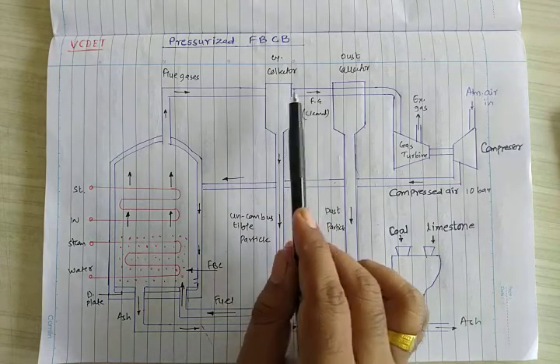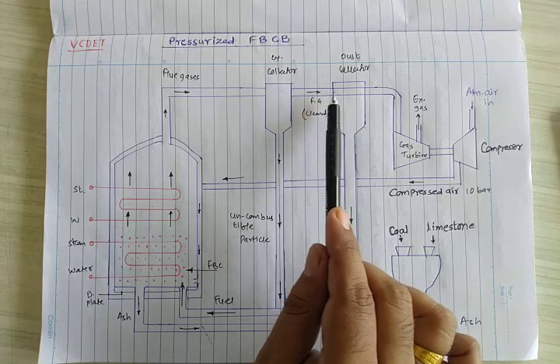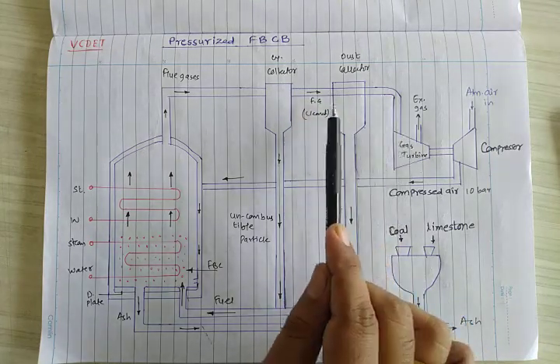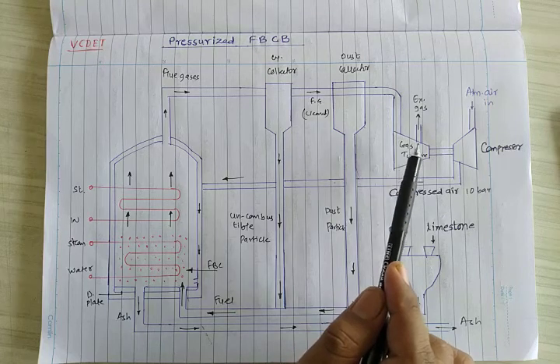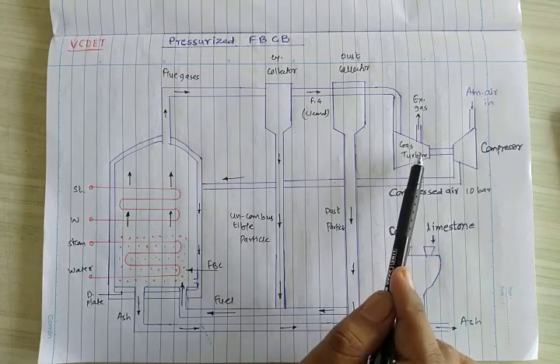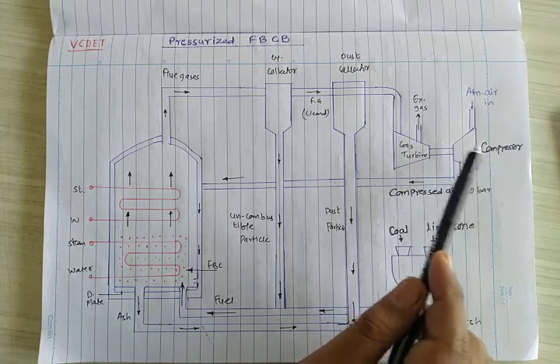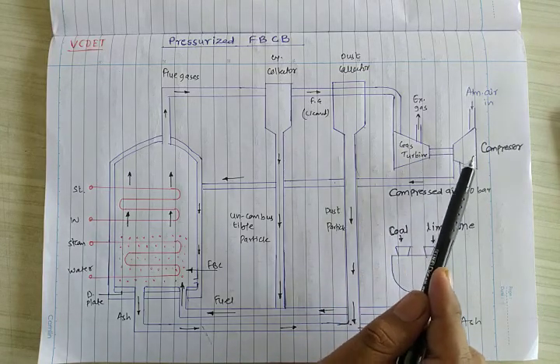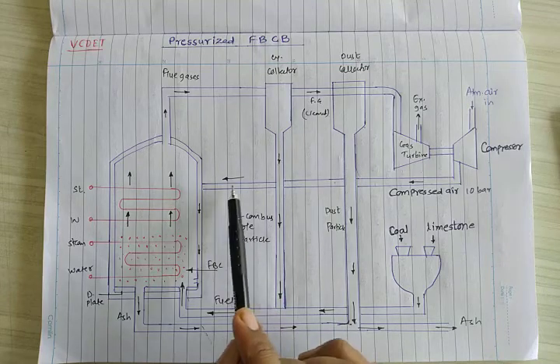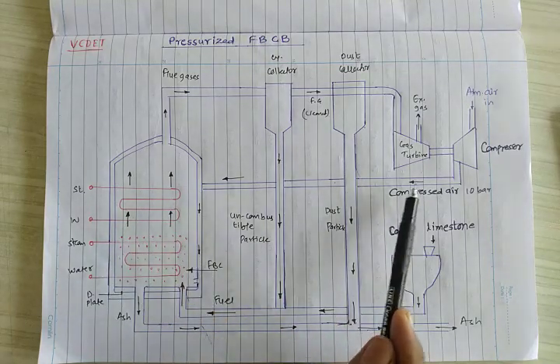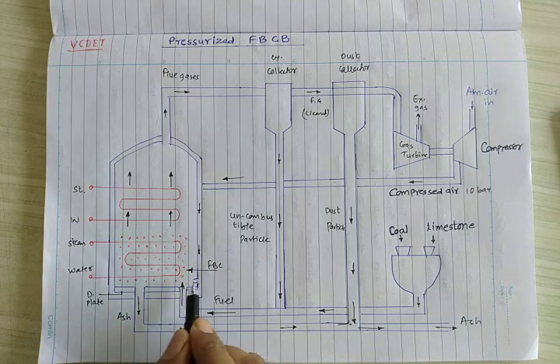The flue gases are forwarded, cleaned, and then forwarded towards the dust collector. From the dust collector they go towards the gas turbine. The clean flue gases are transported towards the gas turbine, which runs the compressor — the compressor shaft is coupled to the gas turbine. The gas turbine drives the compressor, which compresses the air to 10 bar, and the compressed air is sent towards the combustion chamber and the fluidized bed combustion boiler.